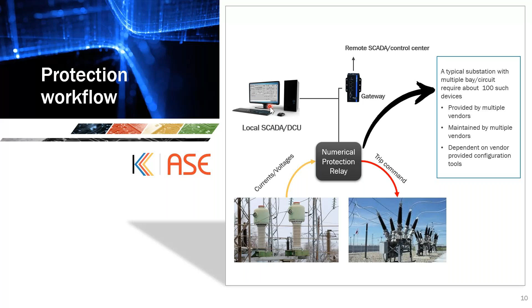So this is a typical protection operation flow where we have these numerical relays. They'll have some additional interfaces where you can have a local SCADA connected, which will give you the real-time information, and the real-time information will also be fed to a remote control center through a gateway. So this is a very simplified protection relay approach in a substation. In a typical substation, there will be multiple bays of circuits that require more than 100 such numerical relays. And typically you will see multiple devices provided by multiple vendors, all maintained by multiple protection engineers, and each of these numerical relays has its own configuration tools, which adds more complexity in the relay configuration management.